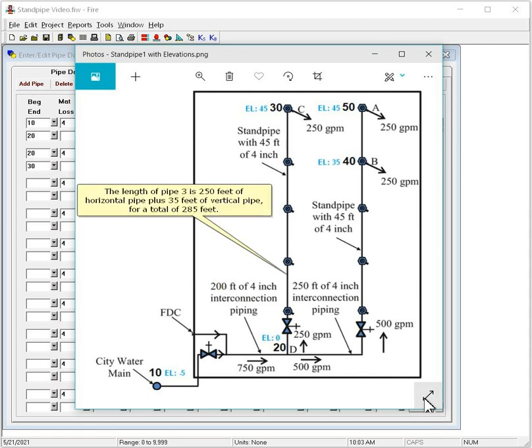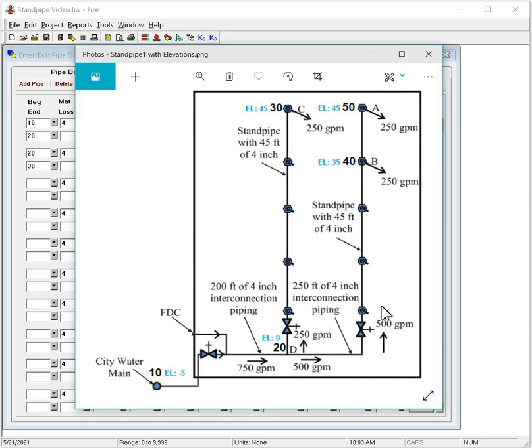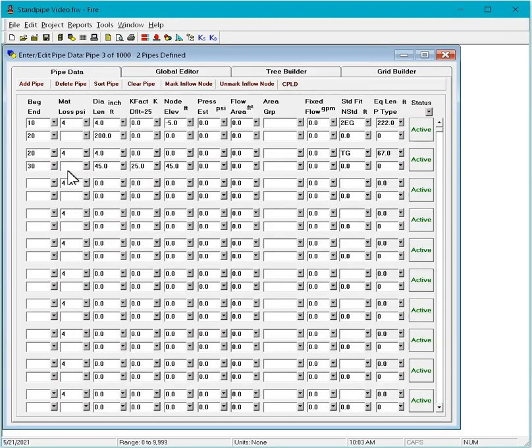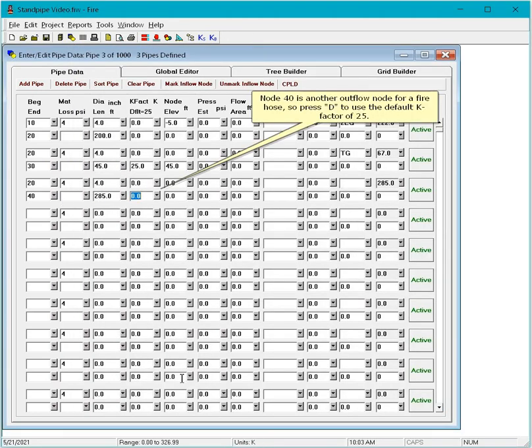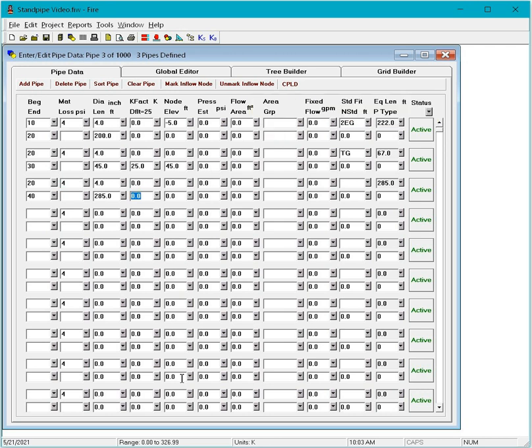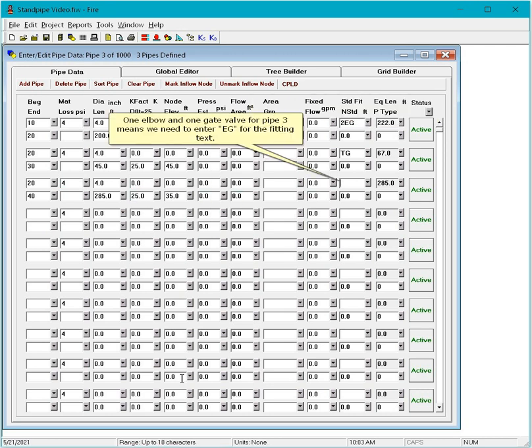The length of pipe 3 is 250 feet of horizontal pipe plus 35 feet of vertical pipe for a total of 285 feet. Node 40 is another outflow node for a fire hose, so press D to use the default K factor of 25. One elbow and one gate valve for pipe 3 means we need to enter EG for the fitting text.